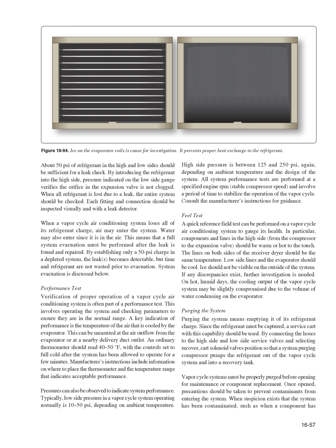When a vapor cycle air conditioning system loses all of its refrigerant charge, air may enter the system. Water may also enter since it is in the air. This means that a full system evacuation must be performed after the leak is found and repaired. By establishing only a 50 pound per square inch charge in a depleted system, the leak becomes detectable, but time and refrigerant are not wasted prior to evacuation. System evacuation is discussed below.